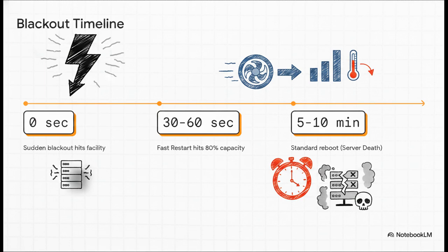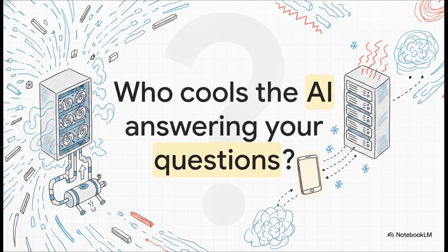So specialized data center compressors are engineered with very specific fast restart logic. They completely bypass standard delays, racing against the clock to hit an incredible 80% of their maximum cooling capacity within a golden window of just 30 to 60 seconds. They literally catch the servers right before they hit critical temperature, saving the brains of the facility in under a minute.